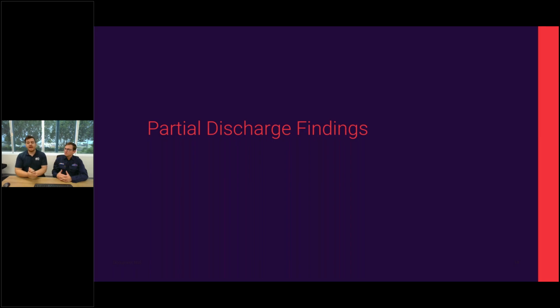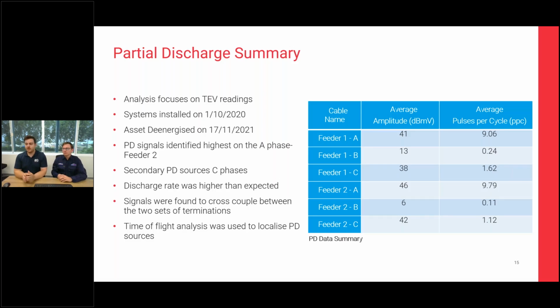So what did we find? It was a lot of data to comb through, honestly. We did a lot of correlation between loading, temperature, and everything else. But immediately we found a very, very high PD source located on a single termination on a single feeder. On the right-hand side you can see feeder 1, A, B, C, and feeder 2, A, B, C—and immediately you can see feeder 2A has the highest readings, followed by feeder 2C and feeder 1A.